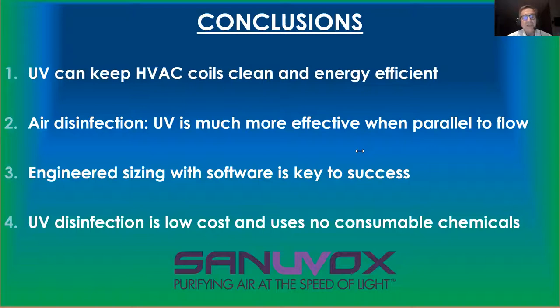But if it's a microbe that is airborne and doesn't stick to a coil, it's not doing a very good job at disinfecting the air. So basically, I think the message you're getting across today to everyone, and we hear it quite often as well, is that coil UV cleaning is not air disinfection. Because as you mentioned earlier, for air disinfection we need to have the lamps parallel to the airflow and not in front of the coil.